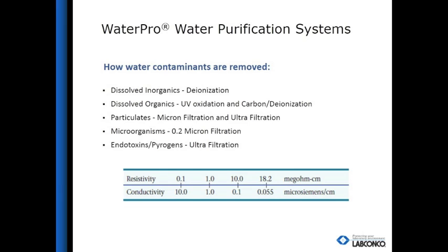Conductivity of water refers to the ability of the solution to conduct electricity. The more ions in the water, the better it conducts. For example, dirty water. Water without ions resists the conductance of electricity. Clean water. Which means the higher the conductivity, the dirtier the water. The higher the resistivity, the cleaner.